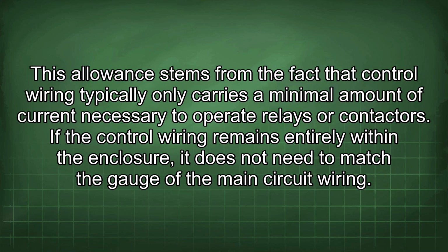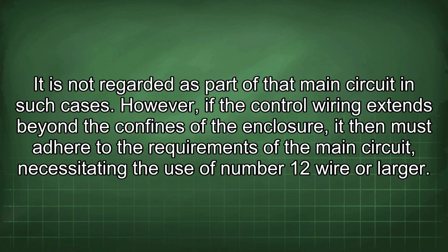This allowance stems from the fact that control wiring typically only carries a minimal amount of current necessary to operate relays or contactors. If the control wiring remains entirely within the enclosure, it does not need to match the gauge of the main circuit wiring. It is not regarded as part of that main circuit in such cases. However, if the control wiring extends beyond the confines of the enclosure, it then must adhere to the requirements of the main circuit, necessitating the use of number 12 wire or larger.